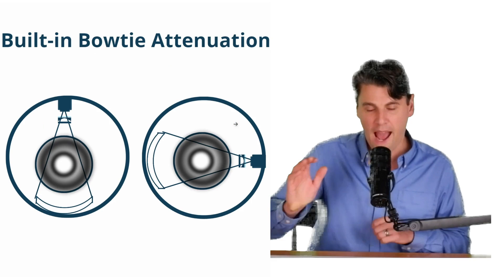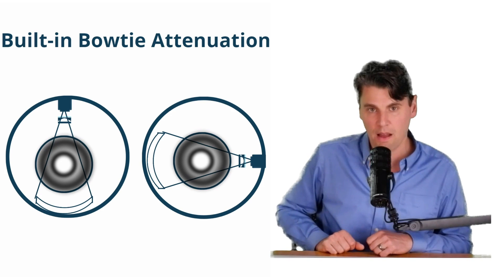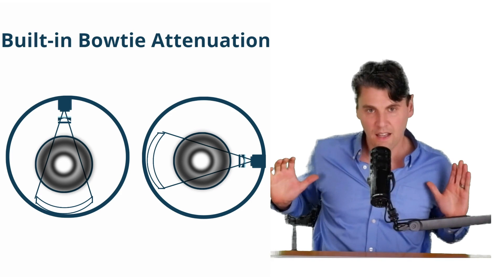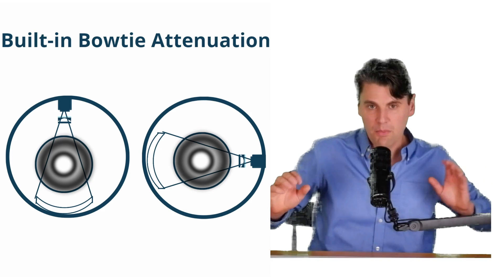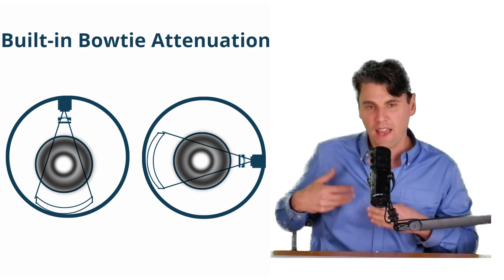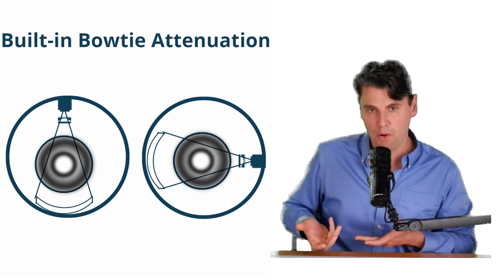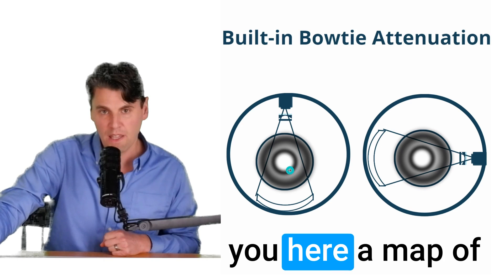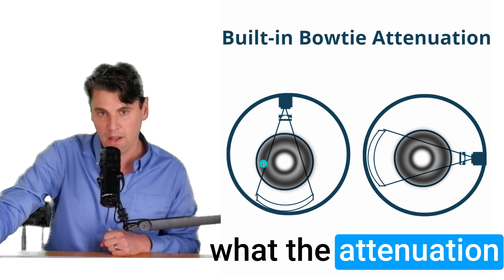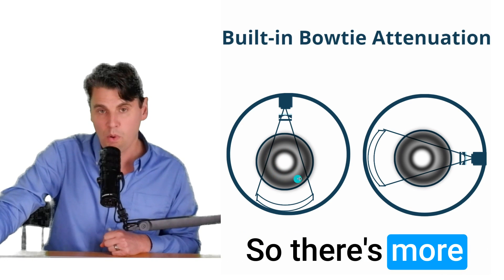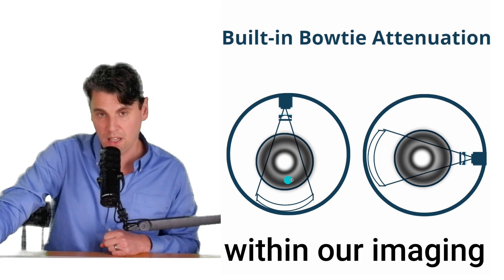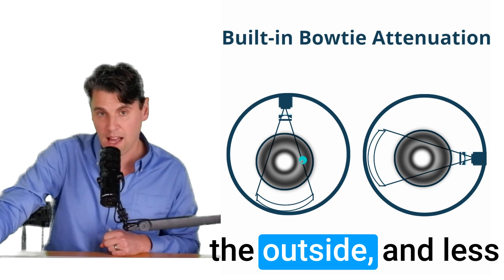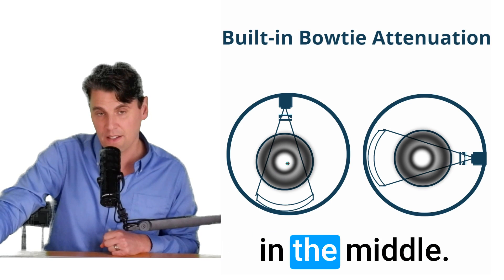And if you remember the back projection process that we talked about in our image reconstruction, where we took the data and we put it back through the volume, think about doing that for the actual attenuation of the bowtie. So we're basically showing you here a map of what the attenuation of the bowtie is like.